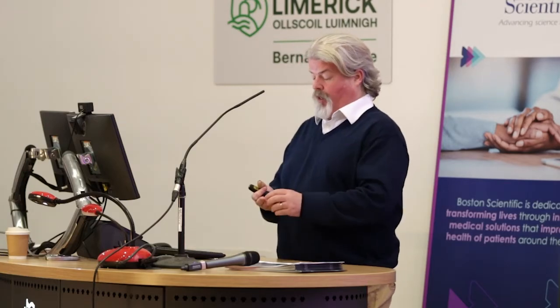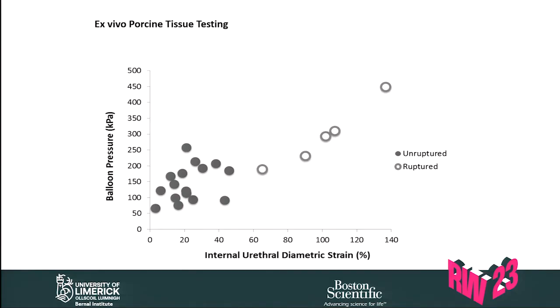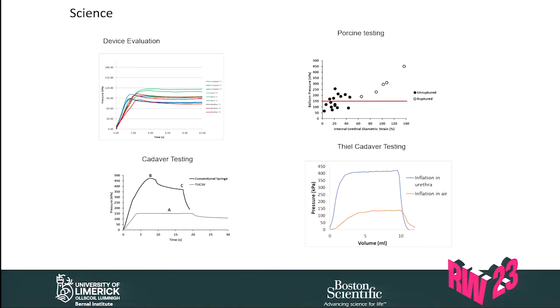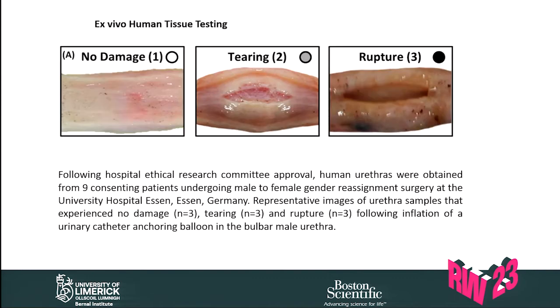So when you look at that as a graph, this is what you come up with. These are the ones that ruptured, and these are the ones that didn't. And so we were getting towards a number that the threshold should be at. We tested a load of commercially available catheters, and they were all at around 120 kilopascals. Then we noticed that the ruptures in the porcine urethras were over 150, and so we set our threshold pressure to that. And then we developed the device, and then we started looking at testing it.